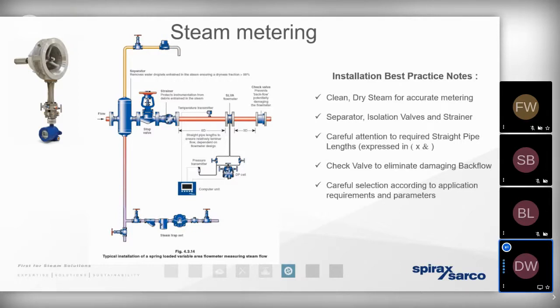For example, if a process is calling for more and more steam over a short period of time, it could well be down to the fact that the heat exchanger is starting to scale up. But the thing we need to bear in mind is that, as with a steam trap, we need to install a steam meter with a number of different ancillaries to ensure that it's going to operate correctly, take a true and accurate reading, and not fail.